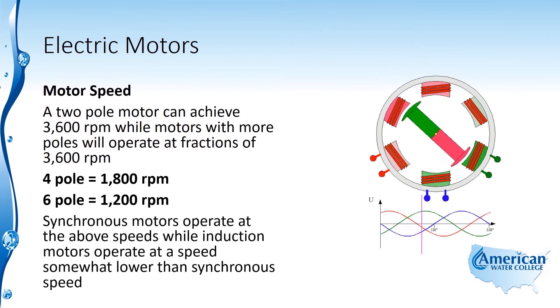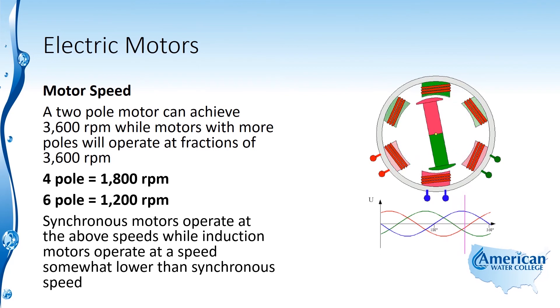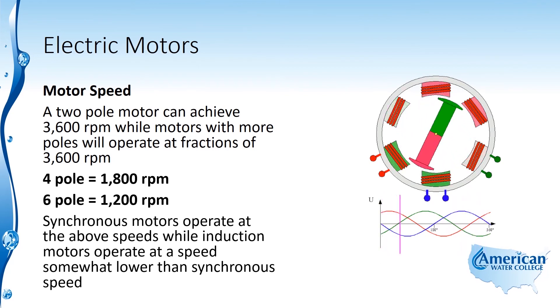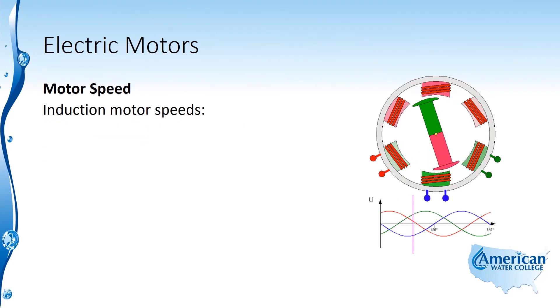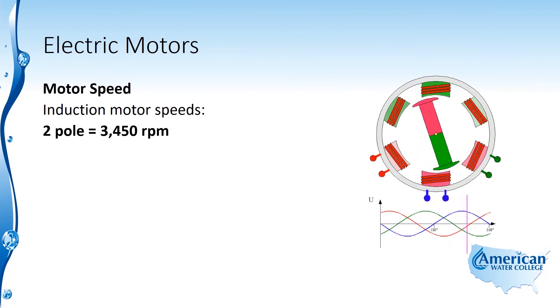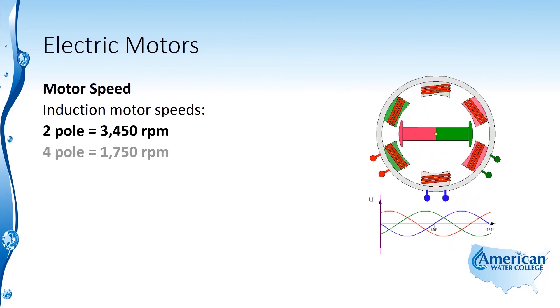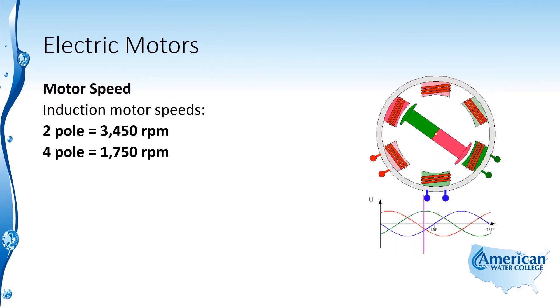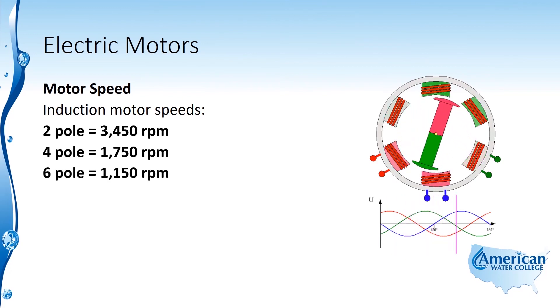Synchronous motors operate at the above speeds, while induction motors operate at a speed somewhat lower than synchronous speed. Induction motor speeds are approximately: two-pole at about 3450 RPM, four-pole at about 1750 RPM, and six-pole at about 1150 RPM.